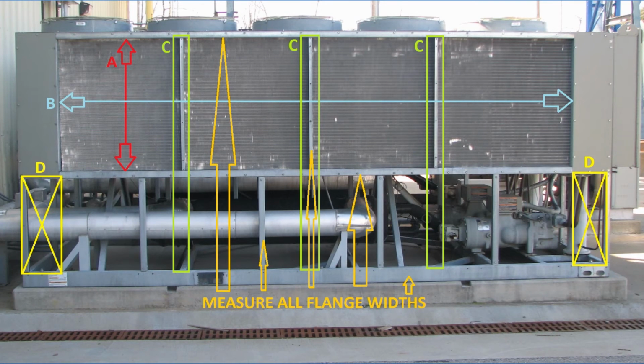Once again, beginning from where the electrical controls are located and working counterclockwise around the unit, measure the inside of the opening for each condenser coil, twice horizontally and twice vertically, to the nearest eighth of an inch.